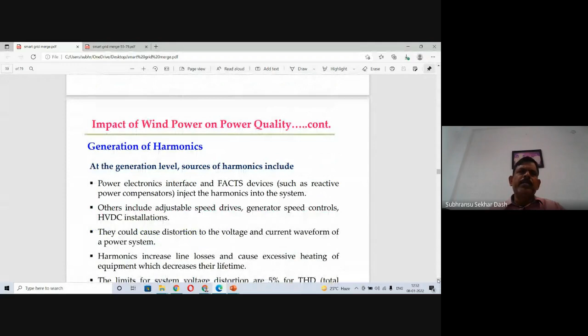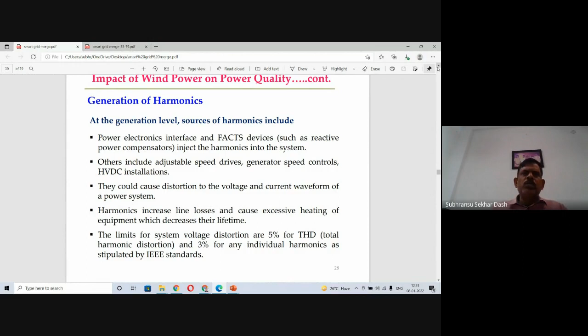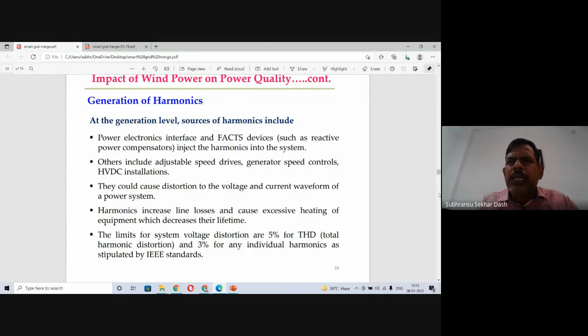The impact of wind power on power quality is very important, as I told you, in terms of how harmonics are generated. At the generation level, facts devices are important sources of harmonics, along with power devices. Others include adjustable speed drives, generator speed controls, and HVDC installations. These could cause distortions, increase line losses, and cause excessive heating of equipment, which decreases their lifetime.